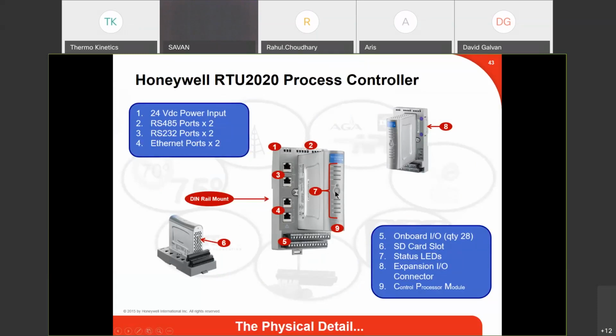This device has an onboard historical data logger. So if something happens, you always have your onboard historical data, and it also sends it via DNP3 to your host system. If something was to happen with your communication, maybe you lost comms for a day or a few hours, the data log is stored here locally. With DNP3, it will store and forward all the information back to your host system automatically. So we have that as well.